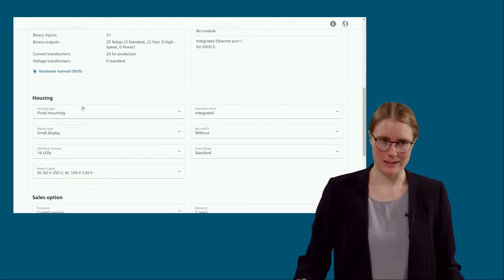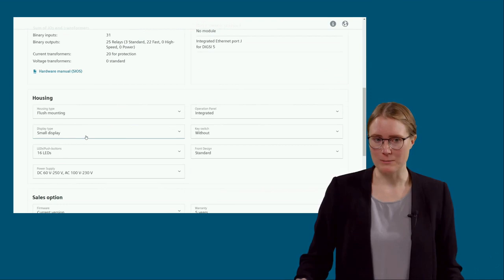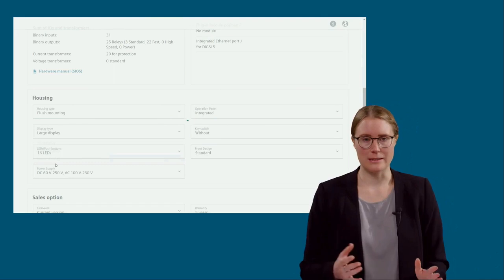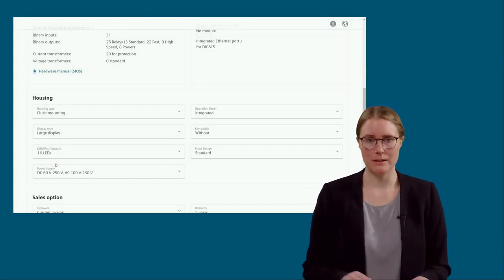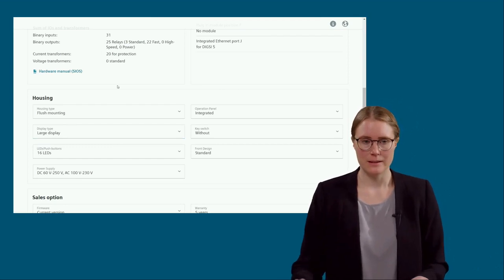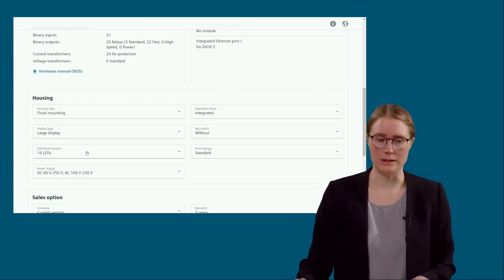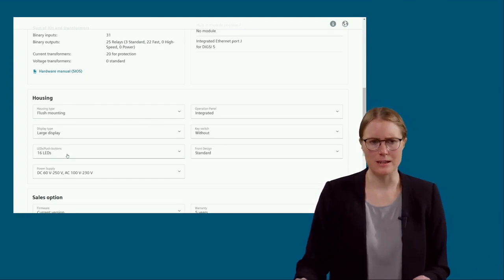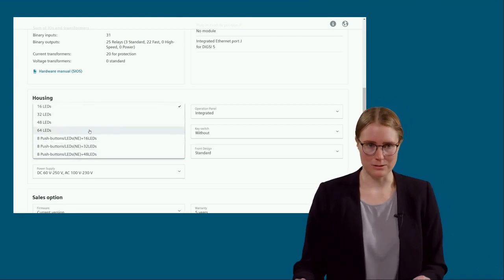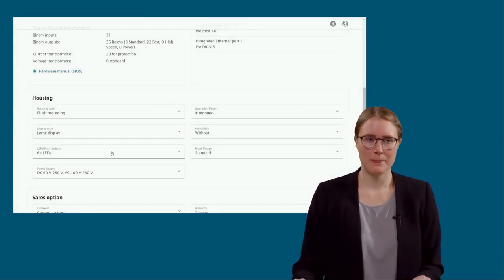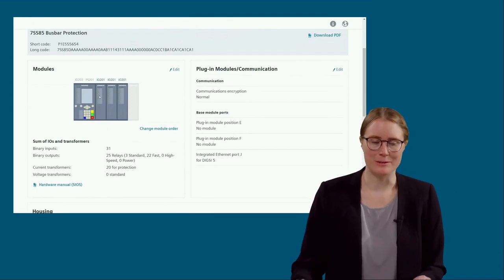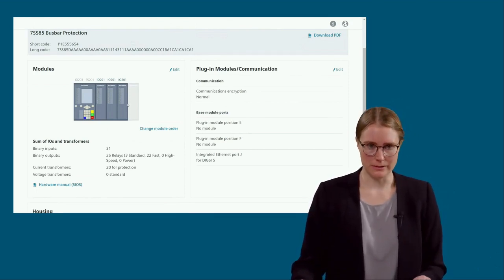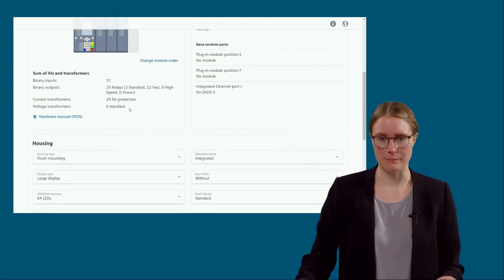And at this page, you can choose, for example, if you want a small display or a big display. We always recommend a large display for the busbar protection, because then you have the chance to really show parts of the single line on your HMI display. Here you also have the option to increase the number of LEDs. At the moment, the pre-default setting is 16, but it is possible to increase this number up to 64. I will do that real quick. And then you can see now all these expansion modules have LEDs as well. So this is really flexible here to increase the numbers.